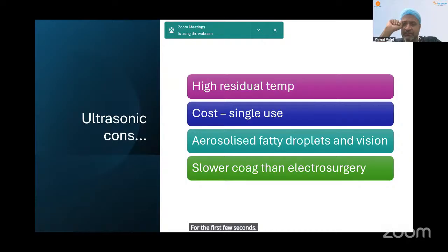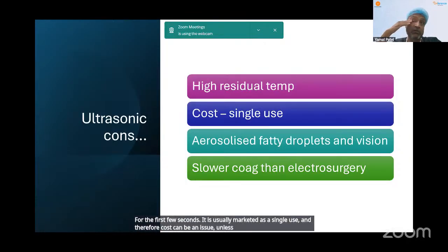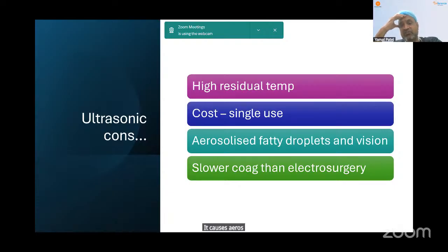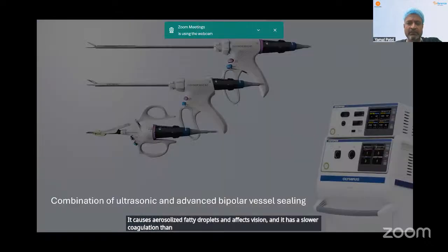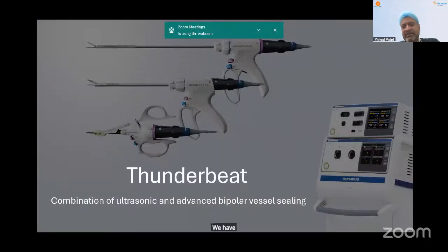It is usually marketed as a single use, and therefore cost can be an issue unless you have a way of reusing it, maybe by using the ETO. It causes aerosolized fatty droplets and affects vision, and it has a slower coagulation than electrosurgical method. We have Thunderbeat as well, which is a combination of ultrasonic and advanced bipolar sealing.